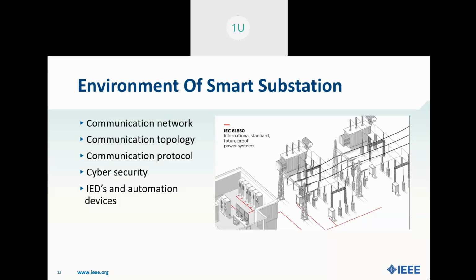The next point is IEDs and automation devices. Modern sensors and other IEDs are the life-giving organs of a digital system. The incorporation of intelligent electronic devices into the substation was one of the early adaptations. The IEC 61850 standard facilitates interoperability between different equipment and suppliers, which makes it possible for these organs to communicate within a substation. By the use of IEDs, the substation is able to integrate, process, and display parameters such as conditions of the equipment, environmental and weather conditions, thermal camera imaging, and cyber and physical intrusion data.